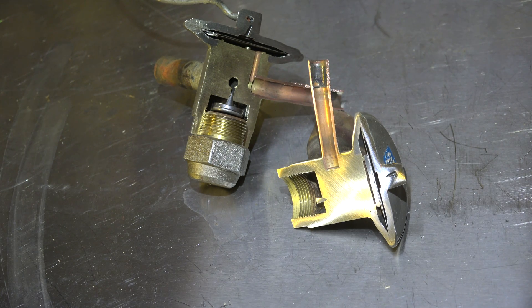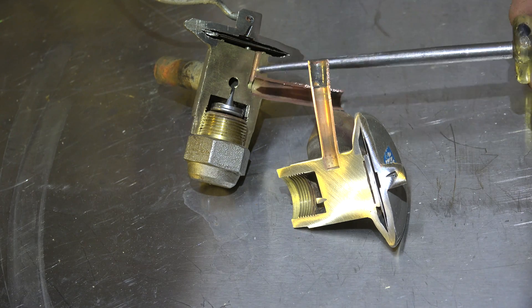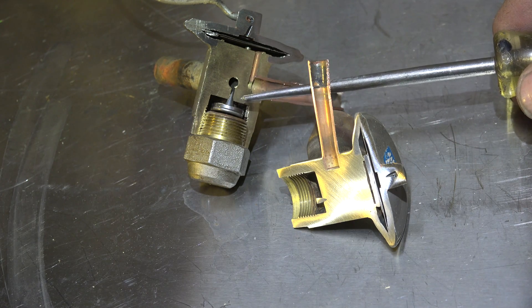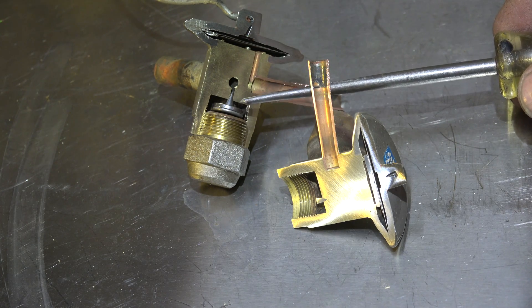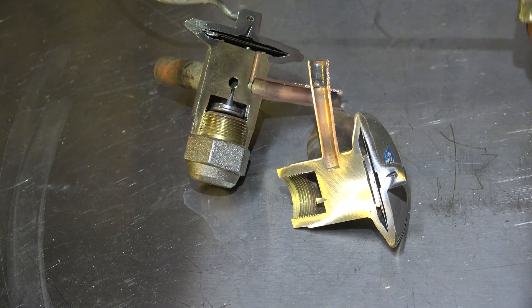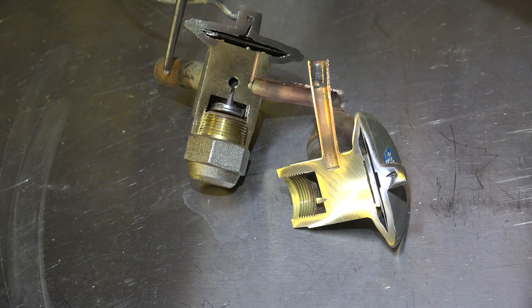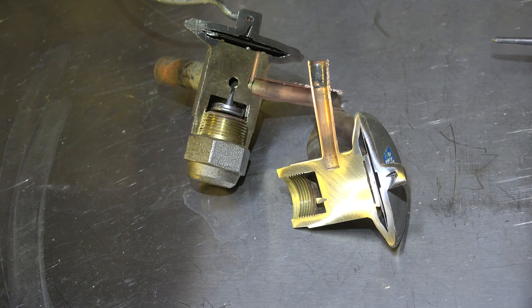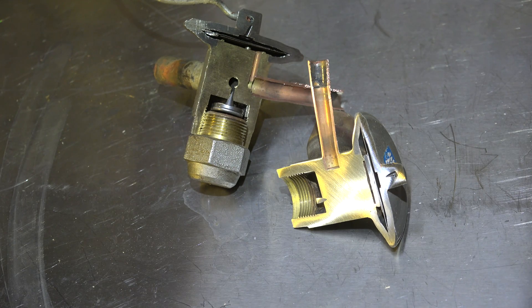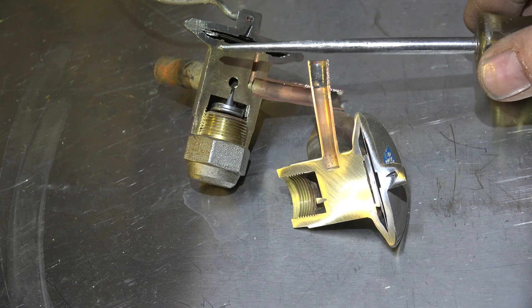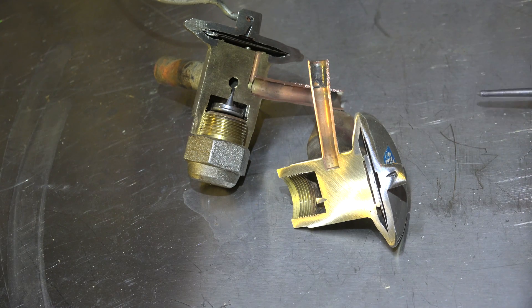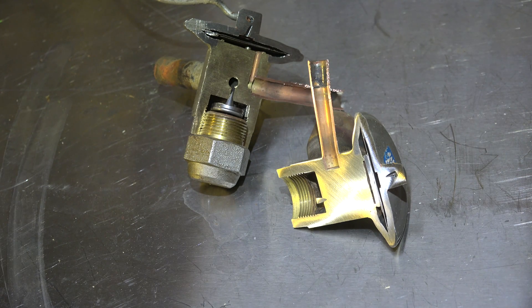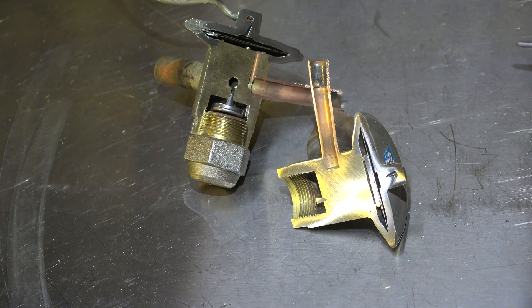Now if this were a bleed TXV, that would mean there would be some connection between this body here, which is the low side evaporating gas, and the high side, which is right here, liquid. There would have to be something there, a tiny hole in this body that went from the high side to the low side or something like that.